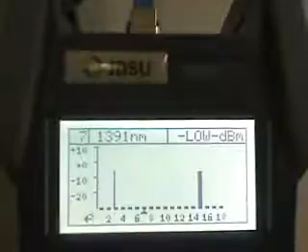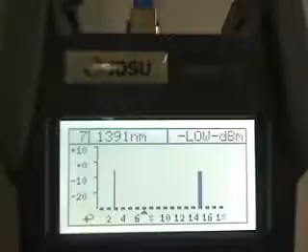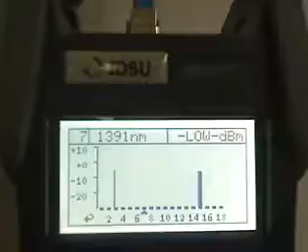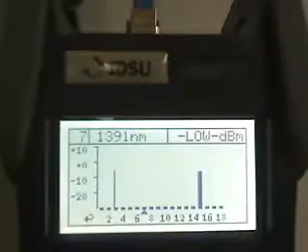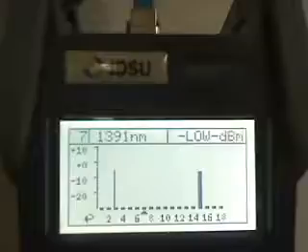The stop button is hit. Channel 15 shows a fat line that represents that the channel is within specifications, which is 6.5 nanometers left and right of the expected channel. So channel 15 is in spec.